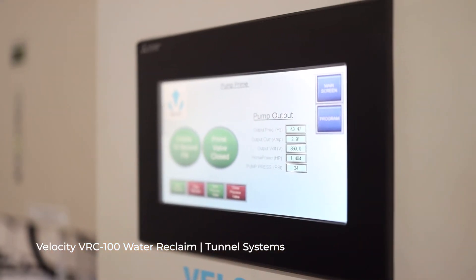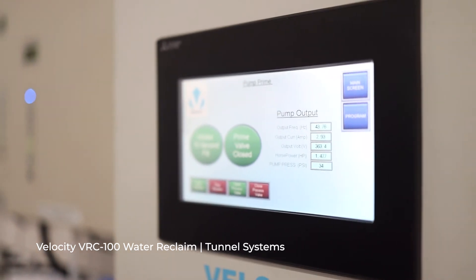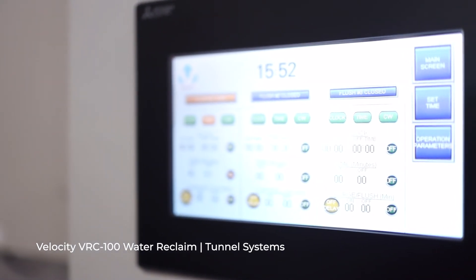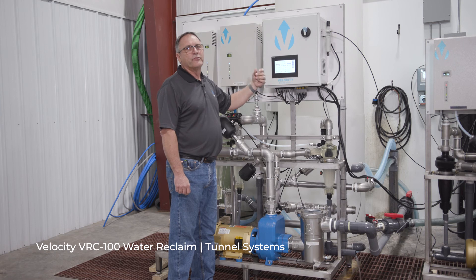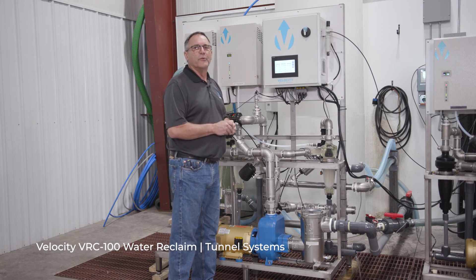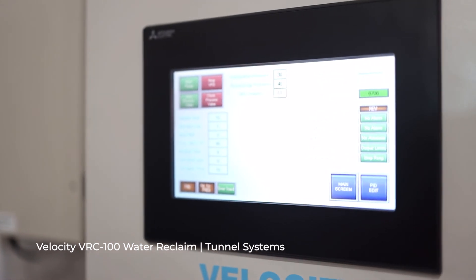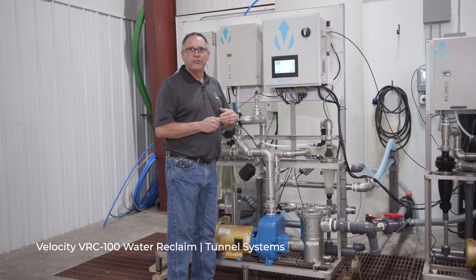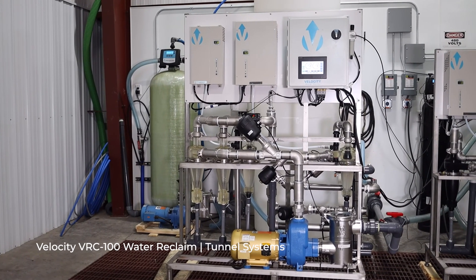The prime function allows you to prime it right from the display, so you don't need a bucket or hose to fill it up. There is programmability for up to three flush functions: one is the primary flush for the trench, and the other two can be for your chain rinse, belt rinse, or any other flush function you'd want to actuate. Operational parameters allow you to increase or decrease pressure depending on the application, tailoring pressure to the need of the unit.